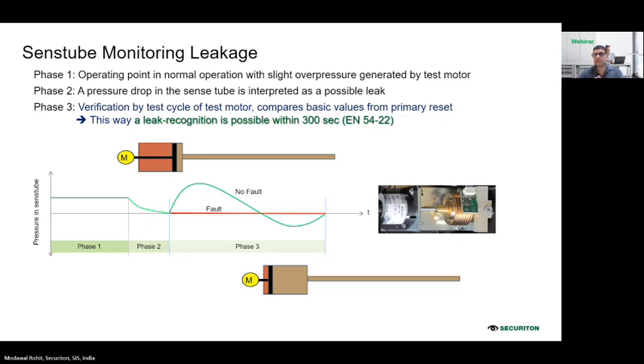So as I said, it will not give you an alarm or fault, but when there is a leakage in the pipe, it will monitor the leakage and you will get the information. This sensing tube is an air-filled capillary line connected to a pressure sensor, so it continuously monitors the air pressure stability inside the tube. If the tube is damaged for any reason, cut or punctured, the internal pressure will drop. This drop in pressure is monitored by the pressure sensor, and it will immediately give you a warning signal.